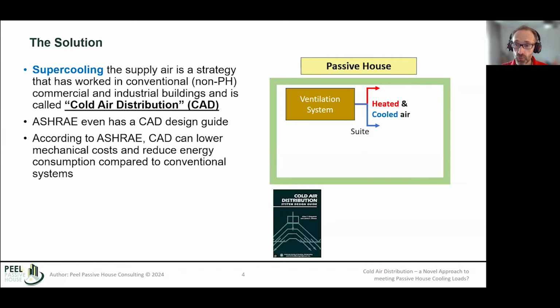So this idea of supercooling the supply air is actually nothing new per se. It's been done in conventional, so non-passive house, commercial and industrial buildings. It's known as cold air distribution, and ASHRAE has a design guide they published in the 1990s on cold air distribution. So it's a well-established strategy, right? And even according to ASHRAE, it's a strategy that can lower mechanical costs and reduce energy consumption. So this is a proven strategy outside of the residential sector.